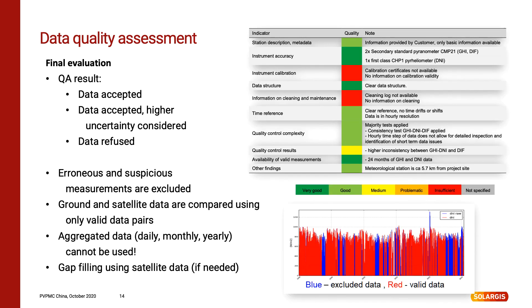The last step of quality assessment is final evaluation of all previously performed tests. All input information is summarized and evaluated in a summary table and each item has its own color flag for visual differentiation. Flagged measurements are sorted into three groups according to their acceptance: data may be accepted, accepted but with higher uncertainty considered, or wrong data is excluded. Accepted data may then be used for comparison with satellite data, for site adaptation, gap filling or for aggregations. Sometimes situations occur where so much measured data was excluded that site adaptation is not possible.